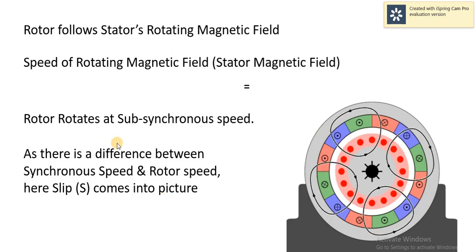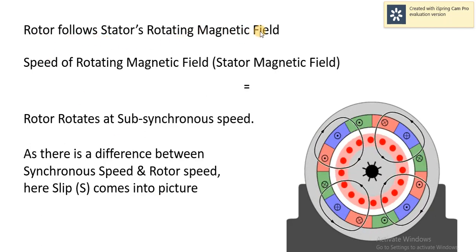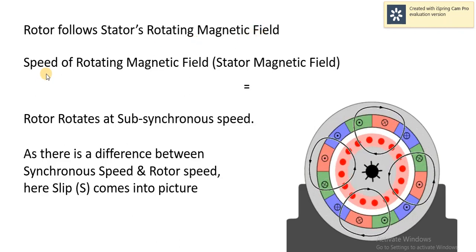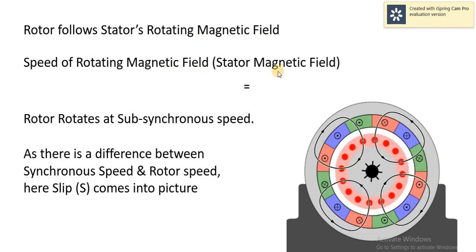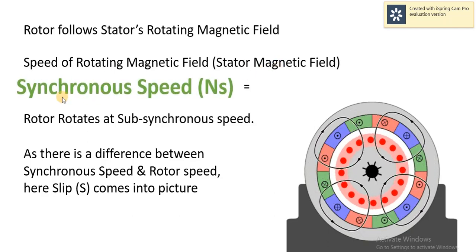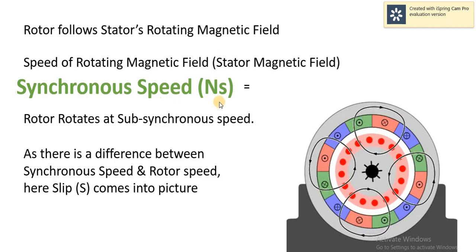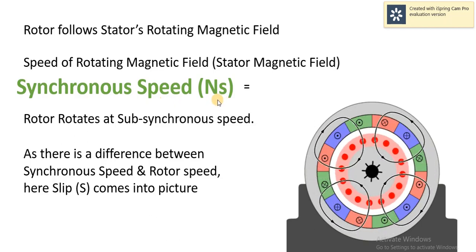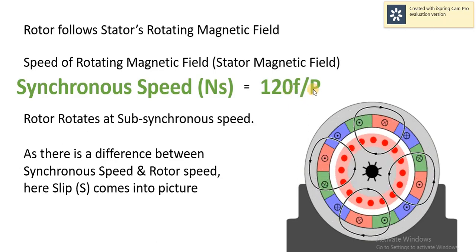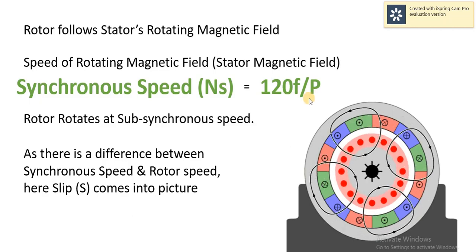The rotor of the induction motor follows the rotating magnetic field. That rotating magnetic field is nothing but the stator magnetic field, and the speed at which the rotating magnetic field rotates is called synchronous speed, denoted by NS. It is given by NS = 120F / P, where F is the supply frequency and P is the number of poles on the stator.